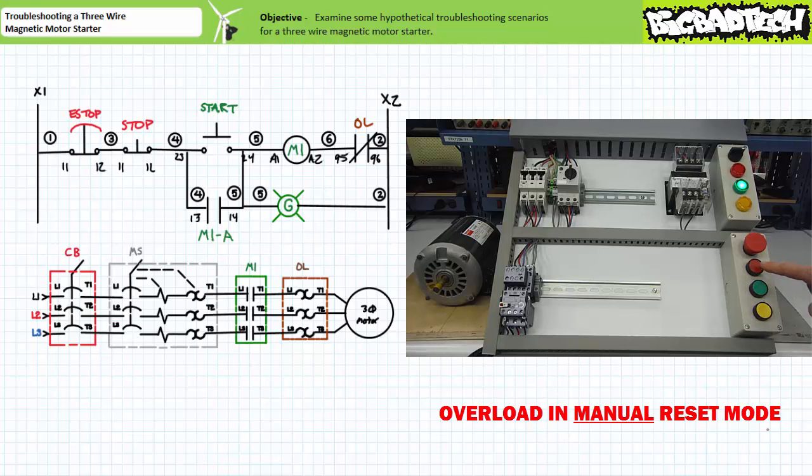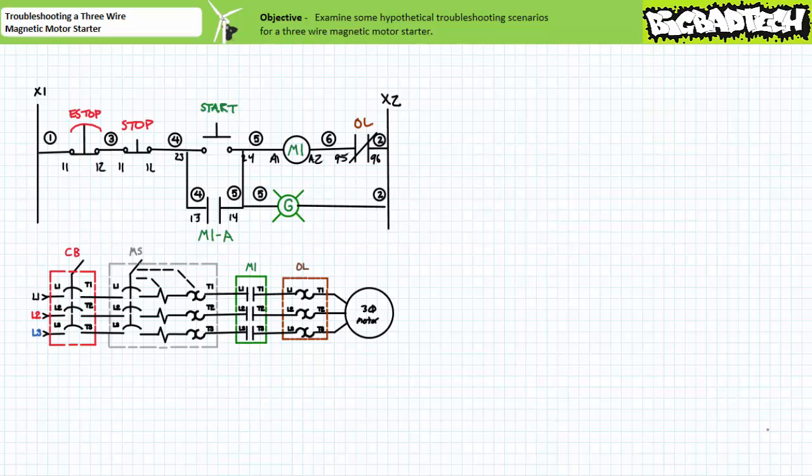Keep in mind, a service call immediately following the removal of the overload-inducing event may be because someone simply forgot to reset the overload in manual mode. Note for both modes, automatic reset and manual reset, the overload should be trip-free, meaning it cannot be held closed while the overload elements are still hot. Let's examine some additional hypothetical troubleshooting scenarios and discuss how this system responds positively or negatively to these situations.